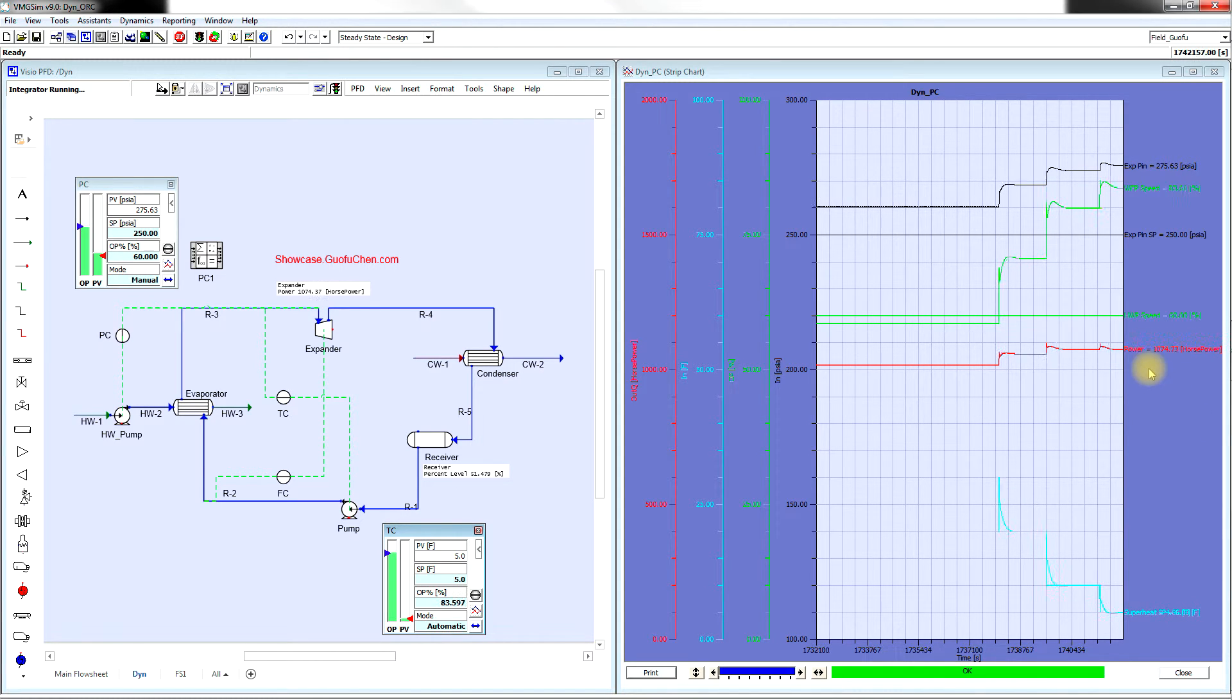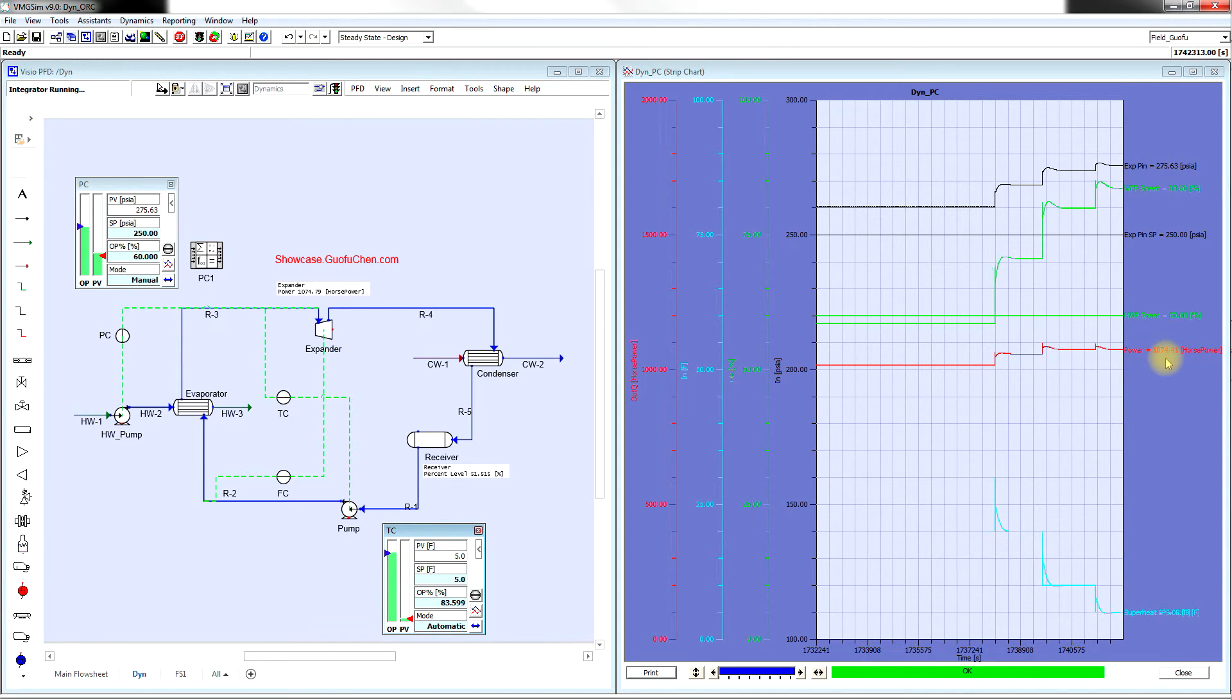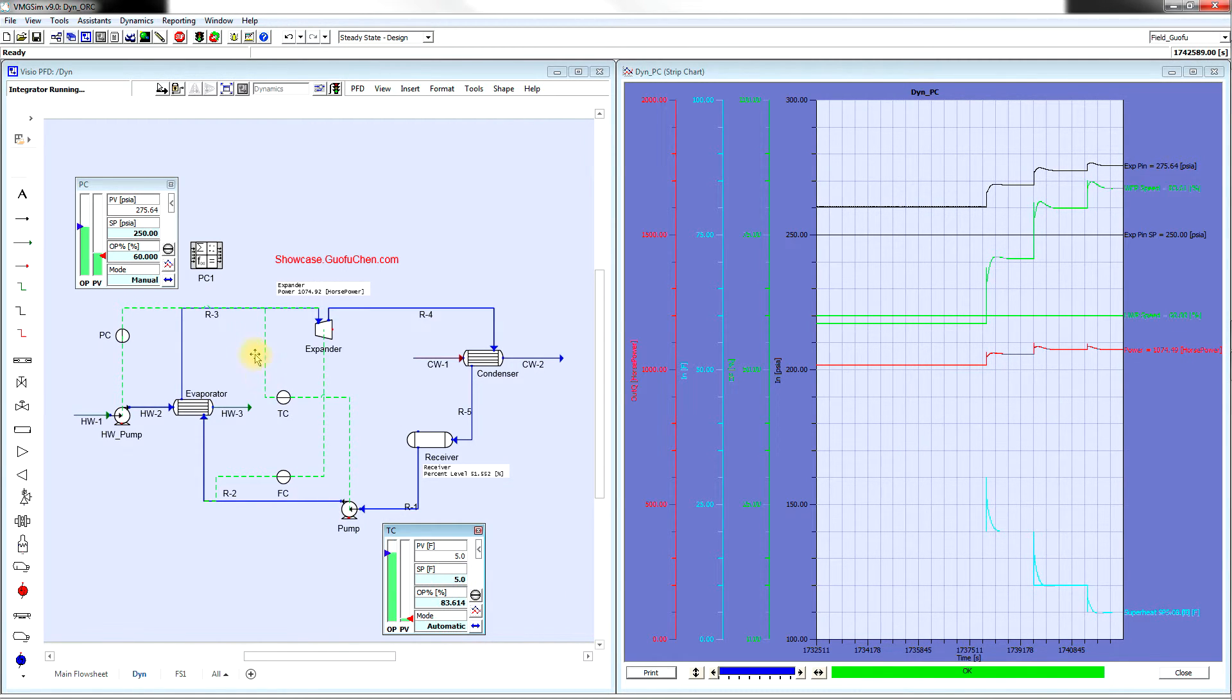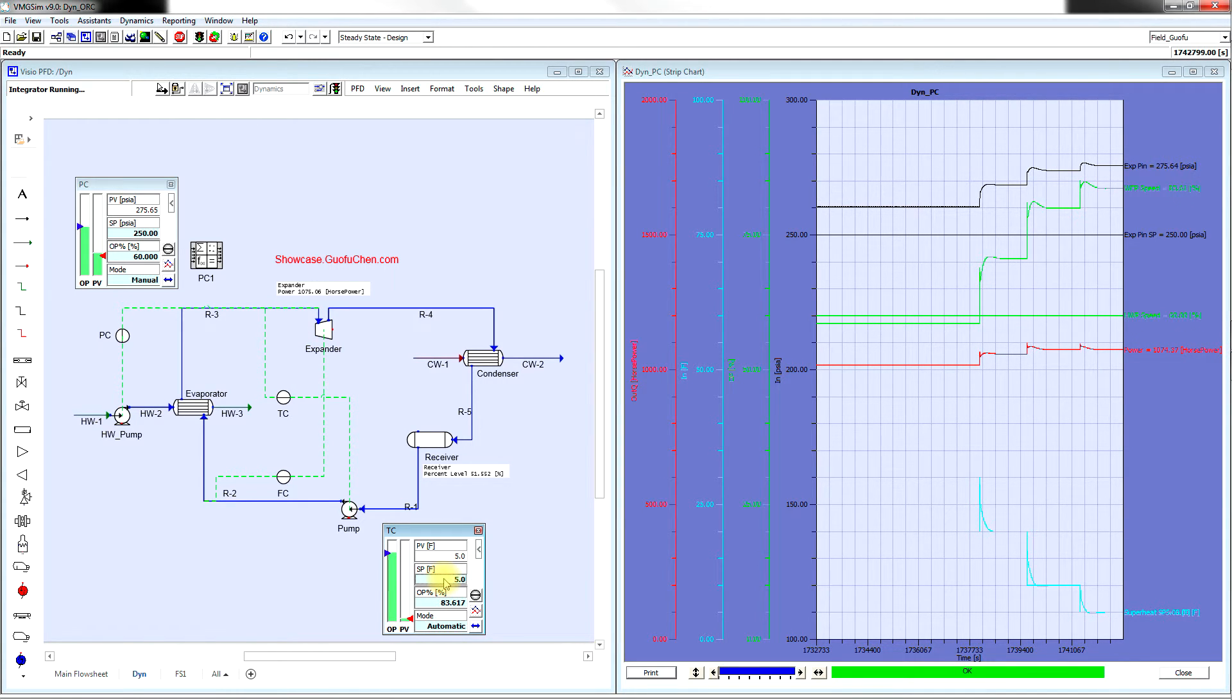It looks like we are still producing the same amount of power output. Since we would like to have a dry gas to the expander, we prefer to sit at a superheat at 10 Fahrenheit.